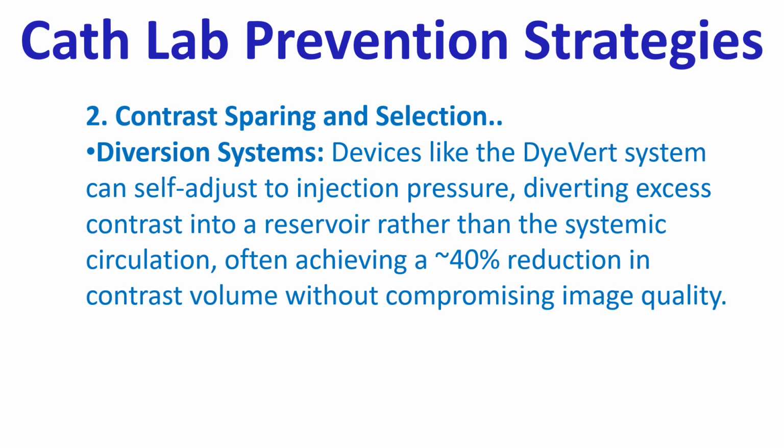Diversion systems. Devices like the DyeVert system can self-adjust to injection pressure, diverting excess contrast into a reservoir rather than the systemic circulation, often achieving approximately 40% reduction in contrast volume without compromising image quality.